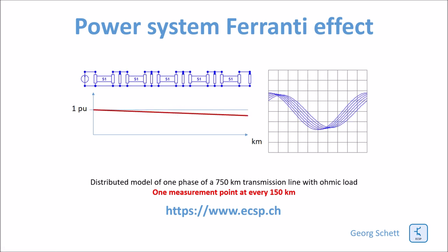If I increase the load — that means I reduce the resistance at the end of the line — you can see that the voltage along the line is reduced. At each segment the voltage is slightly lower, and you can also see a phase shift between the source voltage and the voltage at each segment. The maximum phase shift is achieved at the end of the line. This is typically what you get when the resistance at the end of the line is lower than the surge impedance of the line.